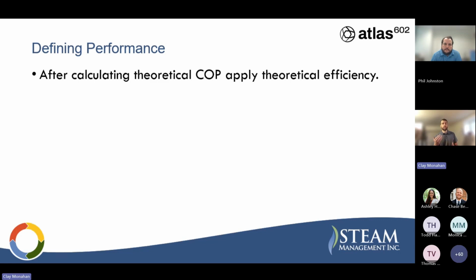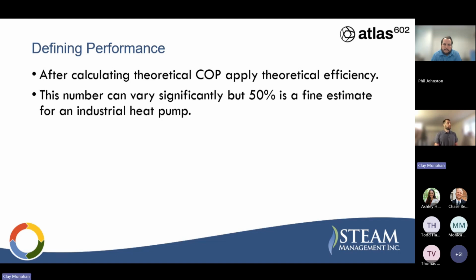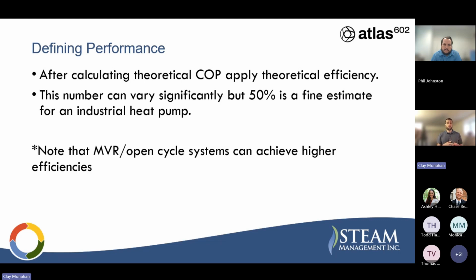Okay, so let's start applying some actual efficiencies to that theoretical efficiency. This number can vary significantly, but as a rule of thumb for a packaged solution, 50% is a fine estimate. It can be lower than that, anywhere in the 40 to 60 percent neighborhood. I'll also say that for an open cycle system, things like MVC/MVR, we can get into those sorts of questions if folks want, these can achieve higher efficiencies due to some advantages of working directly on the fluid that's going into the compressor. But 50% is a fine estimate for most applications. That's going to get you in the ballpark at least.